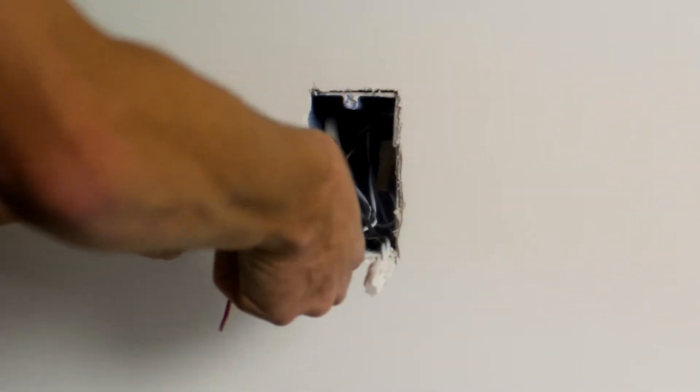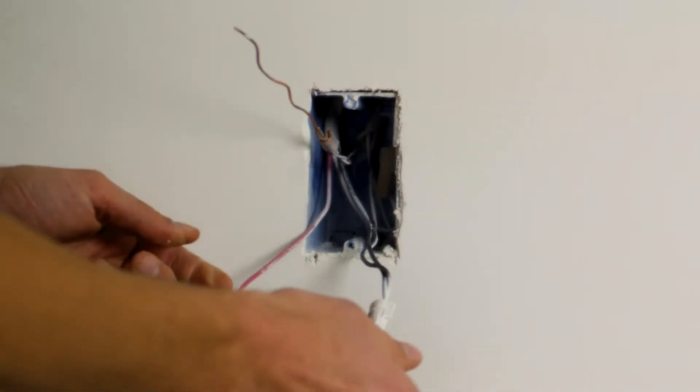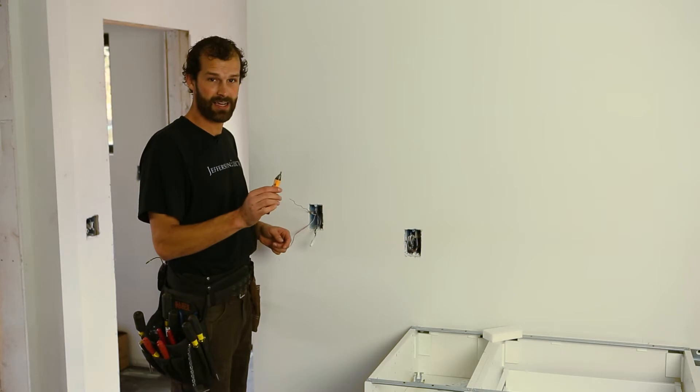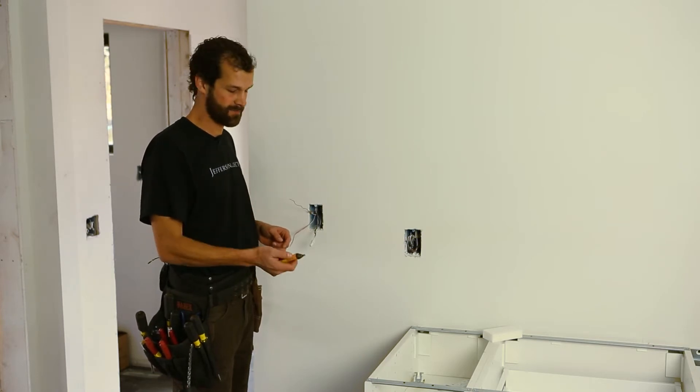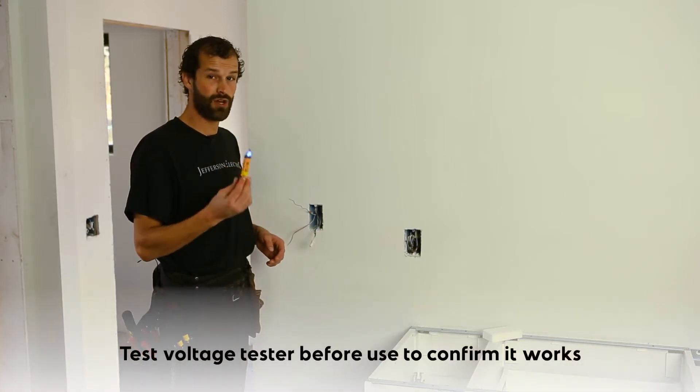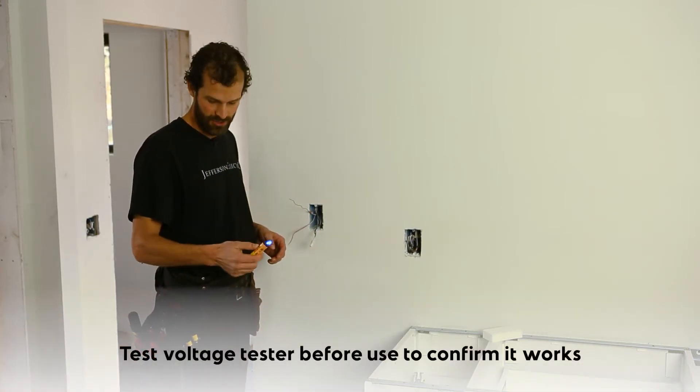Before I get too far into this and handling my hot or ungrounded conductors, I'm using a Klein non-contact voltage detector to verify my conductors are dead. I've already tested this on a known live circuit first to ensure functionality.